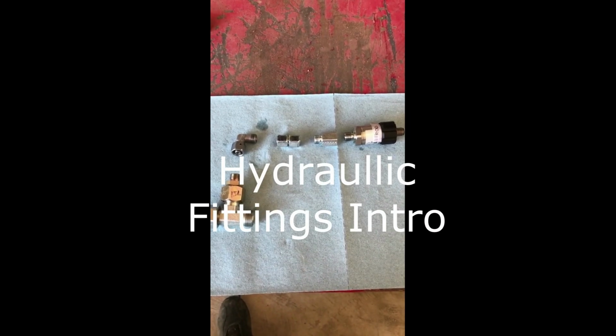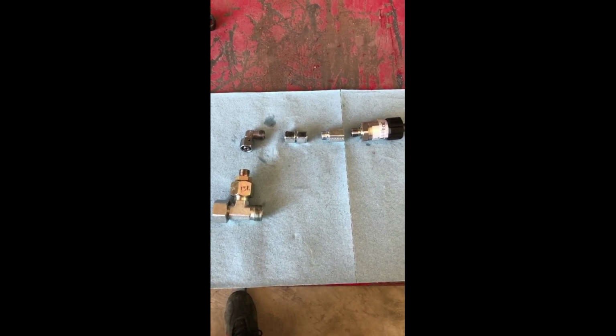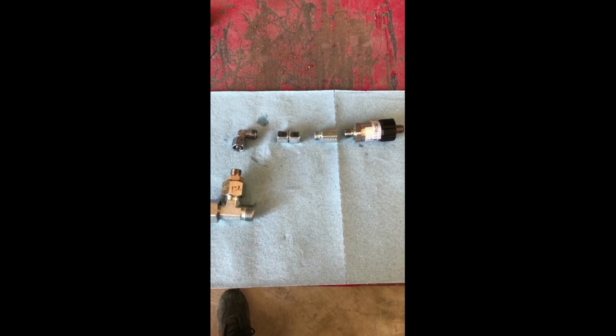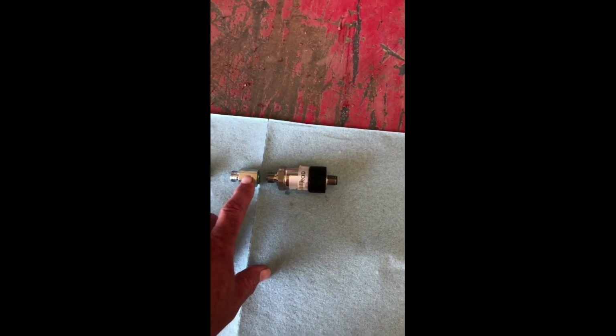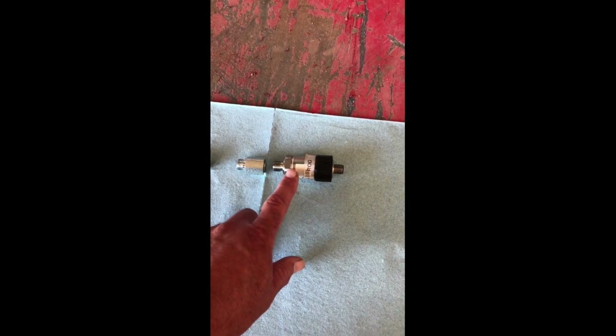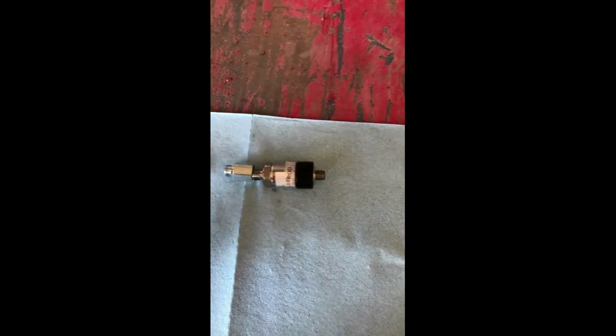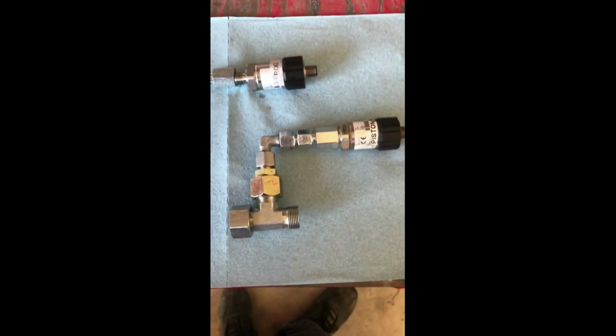Each loader scale will come with a hydraulic fitting kit. That'll be dependent on what machine you have, but it's probably going to consist of something like a T or a flange fitting, an elbow to get to a 90-degree turn, a coupler, and then an adapter that will go on to your pressure transducer. So all this stuff will go together, and then you'll wind up with something like that.